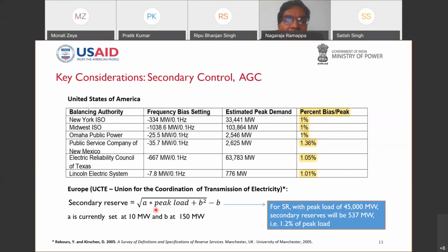In Europe, the Union for the Coordination of the Transmission of Electricity, UCTE, which is coordinating all the system operators in Europe, has come out with an empirical formula which talks about a secondary reserve. It is an empirical formula based upon a deterministic approach, defined as square root of (A times peak load plus B squared) minus B, where A is taken as 10 megawatt and B as 150 megawatt. The reference for that paper is clearly titled A Survey of Definitions and Specifications of Reserve Services. Based upon that, for the 45,000 megawatt demand in the southern region, the secondary reserve will be about 537 megawatt. That is 1.2% of the peak load. Next, please.